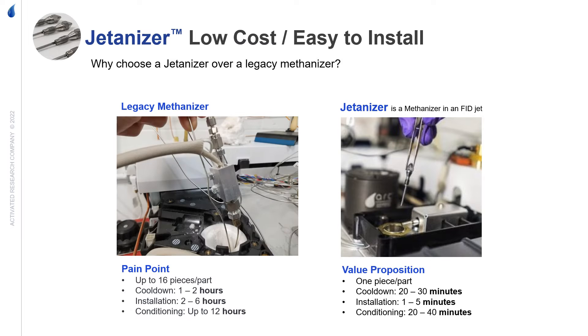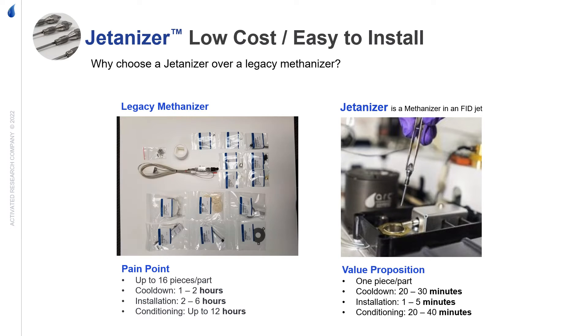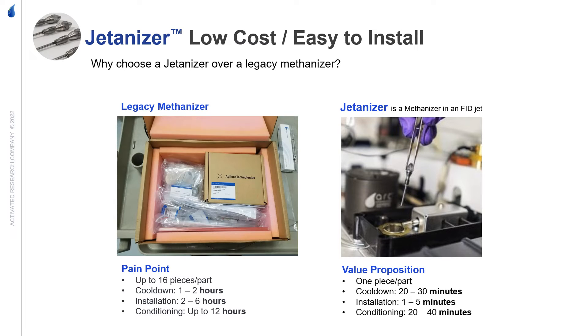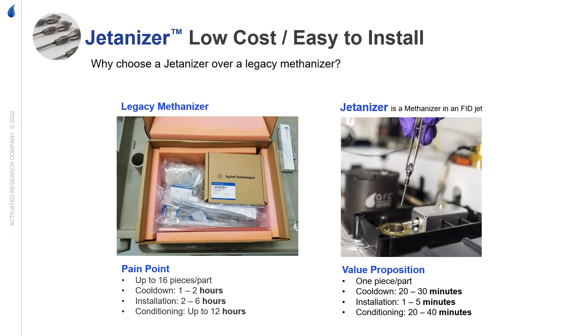One of the biggest benefits of the Jetanizer over traditional methanizers is the affordability and easy installation. Since there is only one piece, the installation can be done in five minutes. It is a simple addition to adapt a GC FID to detect CO and CO2.